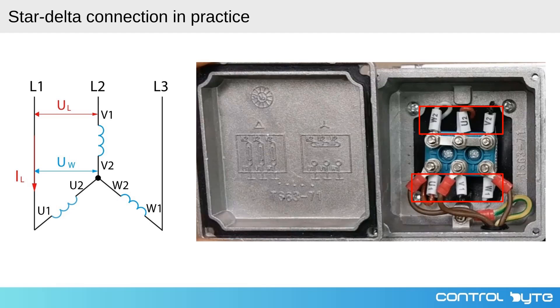The image on the right shows the actual motor terminal box, which contains six terminals corresponding to the ends of the three windings: U1, V1, W1 for one end, and U2, V2, W2 for the other end. In this example, the motor is in a star configuration. The connectors link U2, V2, and W2 together forming the star point, while U1, V1, and W1 are connected to the three-phase power supply.